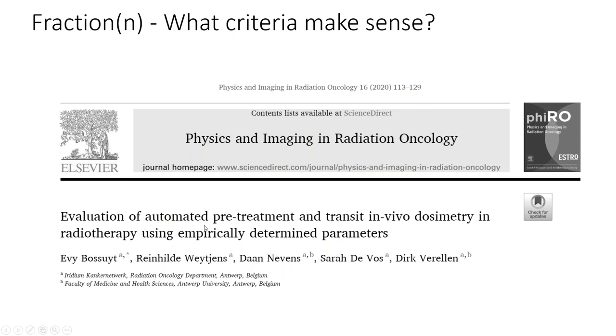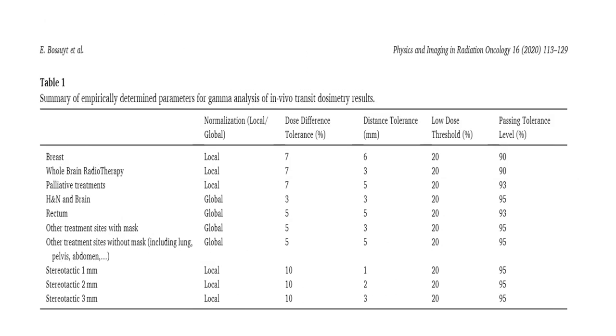The big question was what criteria to use. Three percent and 3mm seemed okay and we were getting reasonable results. The Europeans have been at this longer than us, and one paper provides recommendations that vary a bit from 3 and 3 — slightly more relaxed, but rational. This paper outlines a very methodical approach to what makes sense, and I feel pretty comfortable using it as the basis for setting thresholds for analysis.